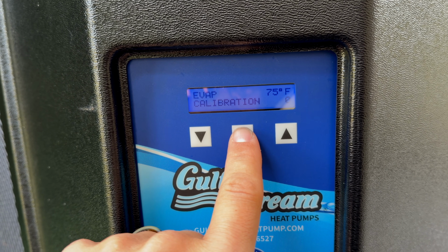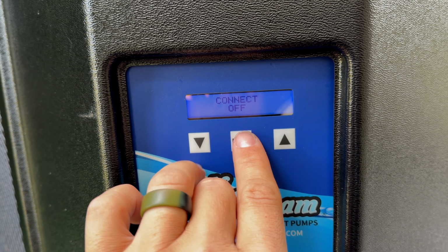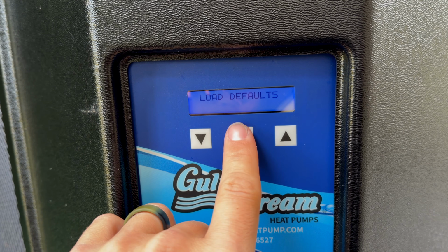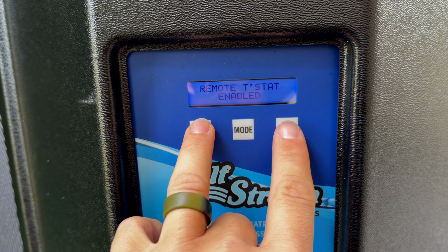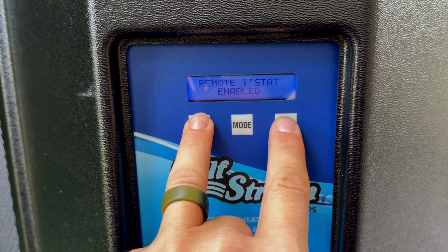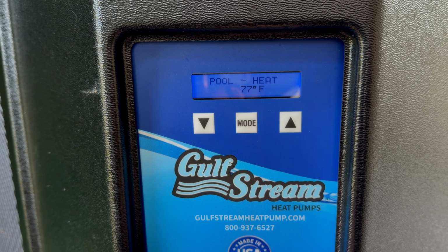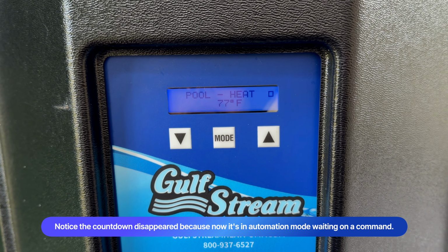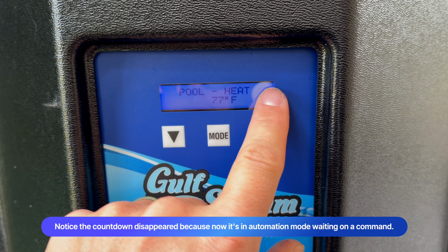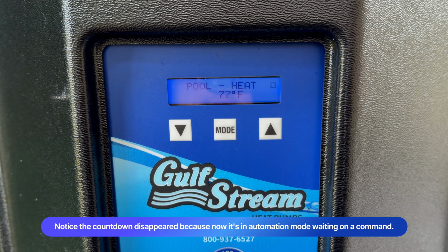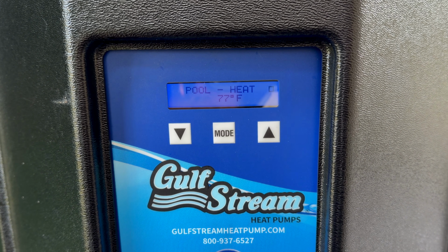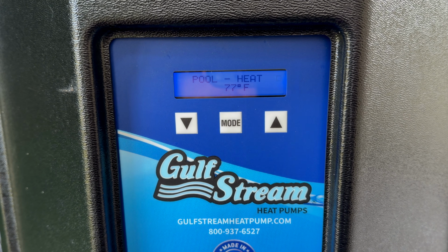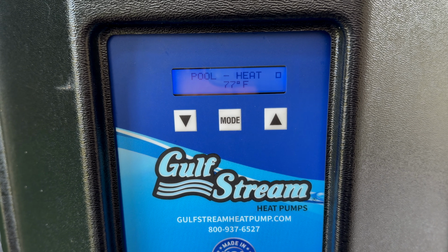So once that's all done, you go ahead, and I like to just go back to where I was, the remote T-stat, make sure that's enabled. Hold these again for 5 seconds. And there we go. So now the heat pump is set up, and you can see the blinking square there. That indicates that it is connected to automation and ready and waiting for command. So that is what you change on the panel to get the automation to control this heat pump.